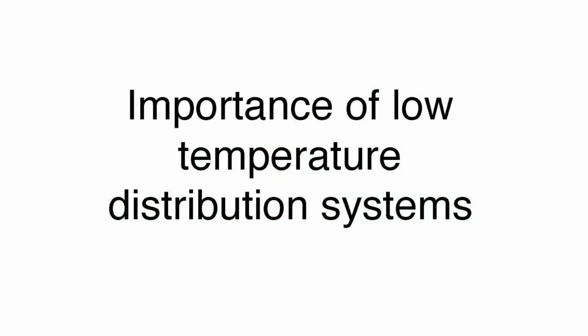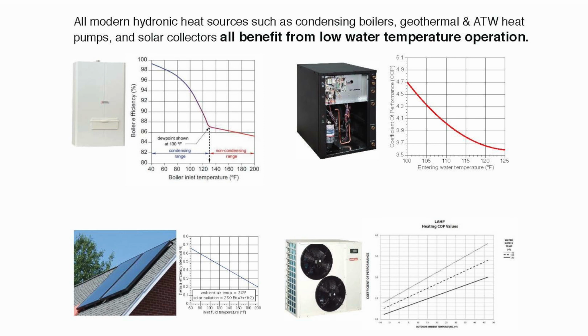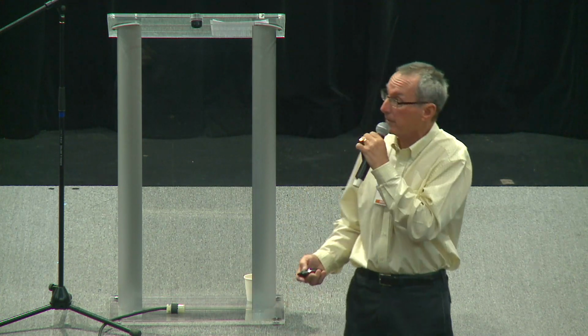Low temperatures. So again, I won't dwell on this. Take a look at all the heat sources that are out there, whether they're heat pumps or ModCon boilers or solar panels. They all benefit from low temperature operation. That is where the global market in hydronics is going. Europeans have recognized that for decades. We're getting there. We are definitely moving in the right direction. But the future of hydronics is not 180 degree water, 200 degree Fahrenheit water. It's 100 degree water, maybe 120 degree water.